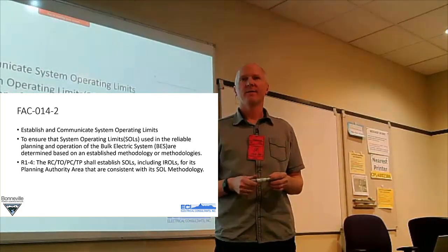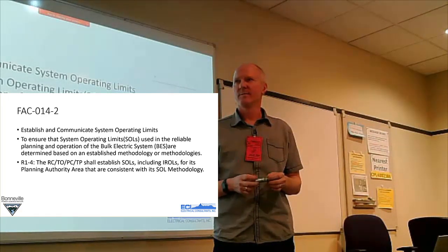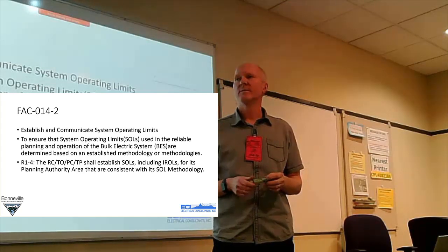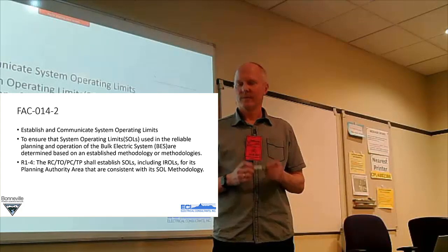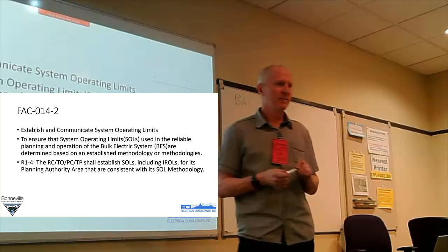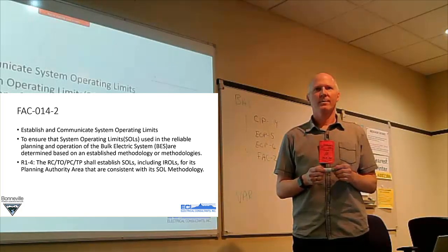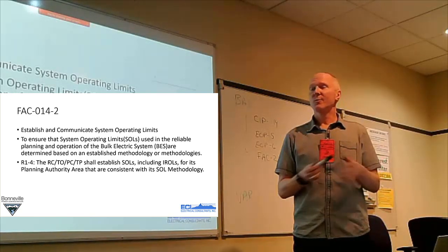If you have cascading due to the loss of a facility, then that could warrant an IROL development, which is not just thermal evaluation. Okay, so an IROL is a kind of SOL. It's essentially the complicated ones. And IROLs are set by the RC. TOPs don't set them. TOPs set SOLs. Are SOLs always only thermal then? No, they can be stability limited. Voltage stability, transient stability. Or voltage.